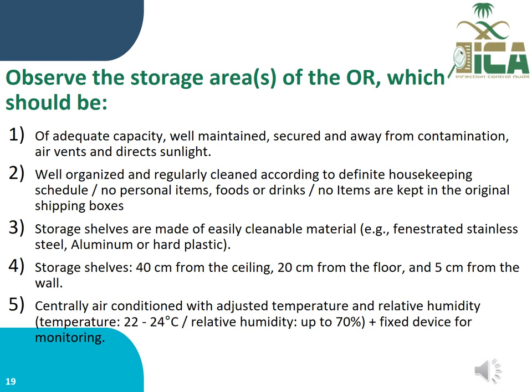Observe the storage area of the OR. It should be: (1) of adequate capacity, well-maintained, secure, away from contamination, away from air vents, and away from direct sunlight; (2) well-organized and regularly cleaned according to a defined housekeeping schedule, with no personal items, food, or drinks, and no items kept in original shipping boxes; (3) storage shelves made of easy-to-clean material such as fenestrated stainless steel, aluminum, or hard plastic; (4) shelves positioned 40 cm from the ceiling, 20 cm from the floor, and 5 cm from the wall; (5) centrally air conditioned with temperature from 22 to 24°C, relative humidity up to 70%, plus a fixed device for monitoring.